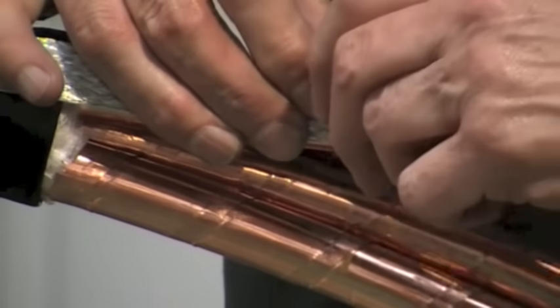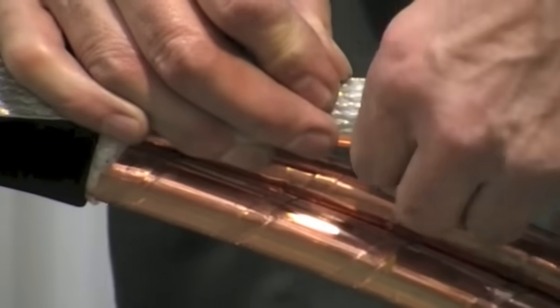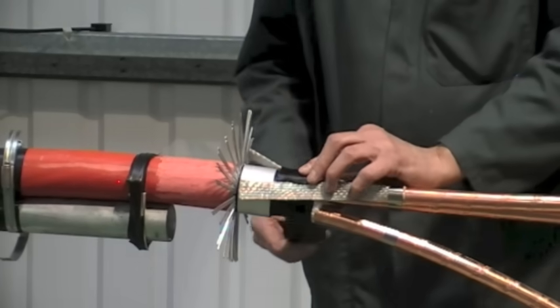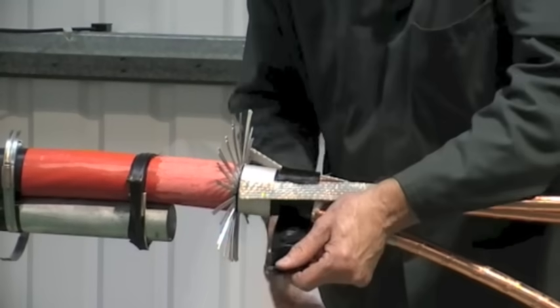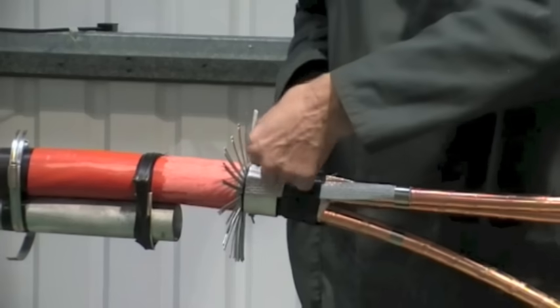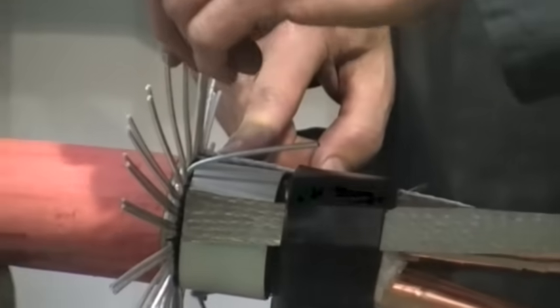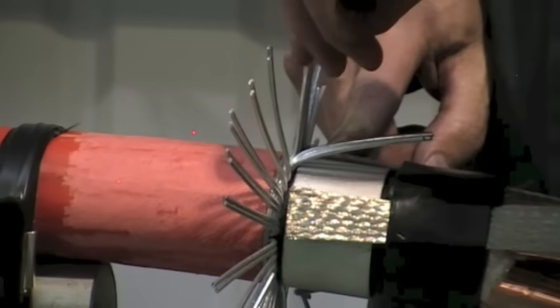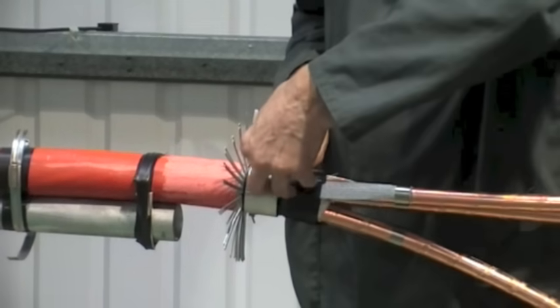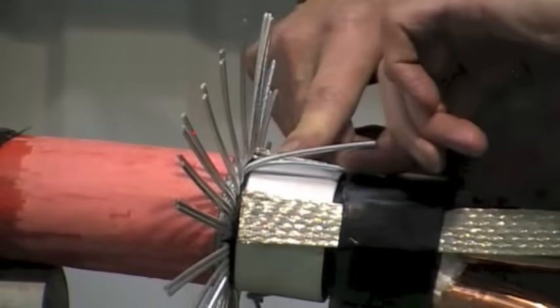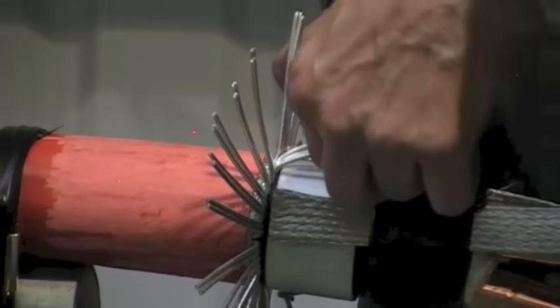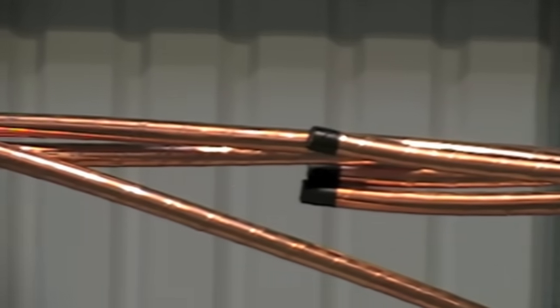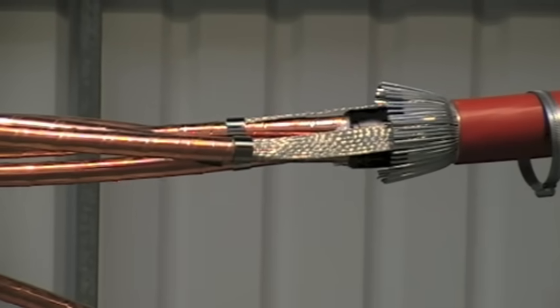Lay the copper earth straps onto the copper tape screens, securing with the constant force roll springs supplied. Apply further mastic over the braids and the earth braids will be clamped down at a later stage along with the armour wires. Do this at both sides.